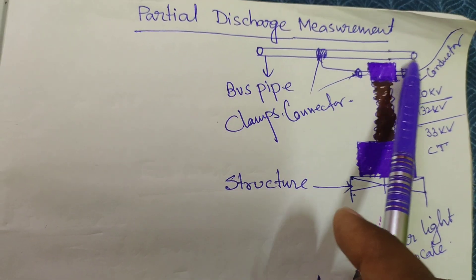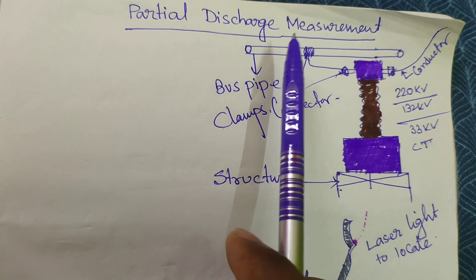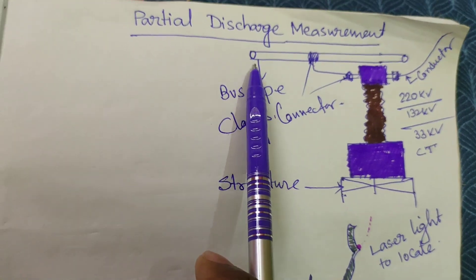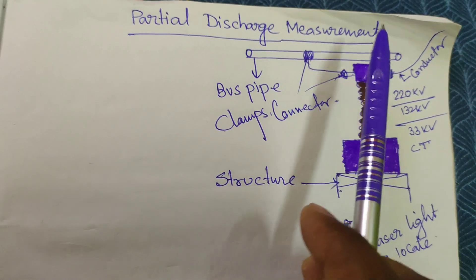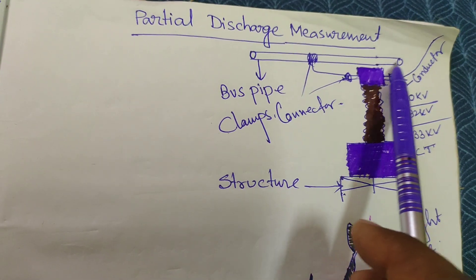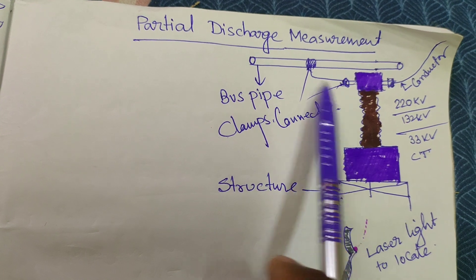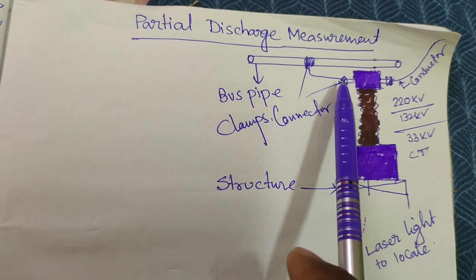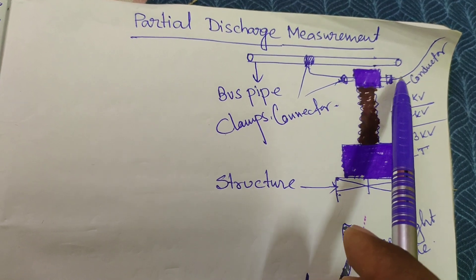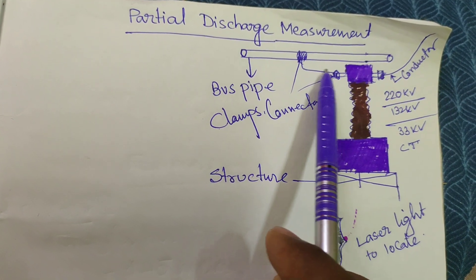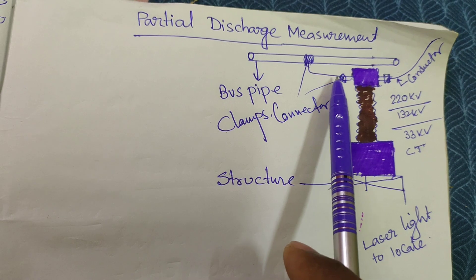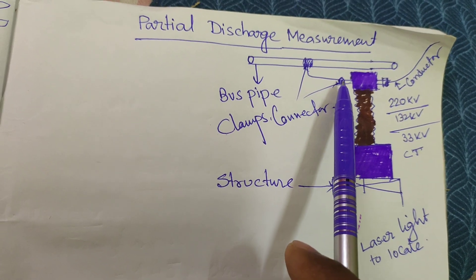I have drawn a diagram of a bay — the outgoing CT. This is the bus bar; it may be the 3-inch IPS tube, 2.5-inch IPS tube, 1.5-inch, or 4–5 inch according to requirement. This is the bus bar aluminium pipe. These are the conductors — it may be Panther, Zebra, Moose — whatever the connection, depending on the current carrying capacities of the outgoing feeders. These conductors are fixed by clamp connectors.